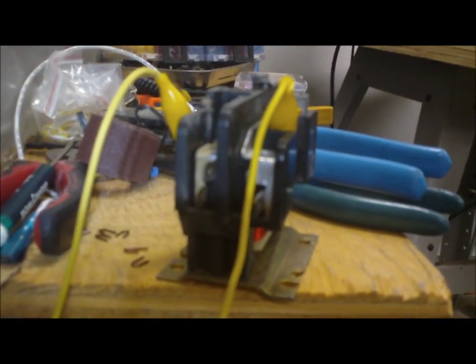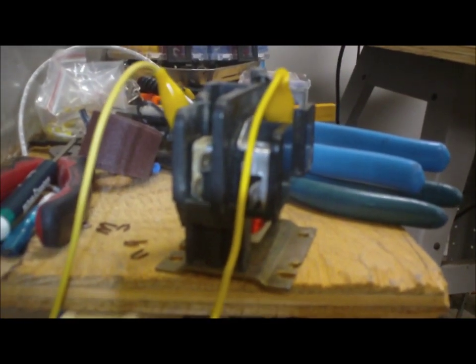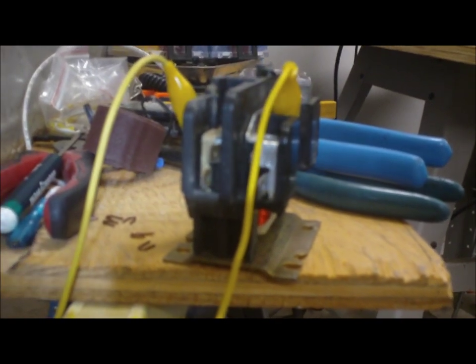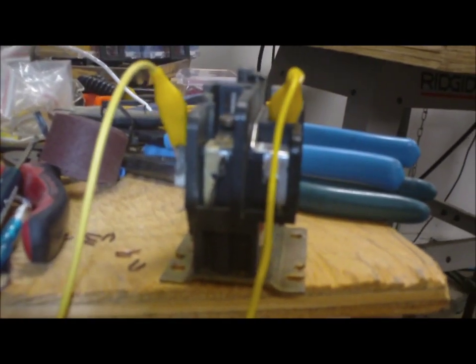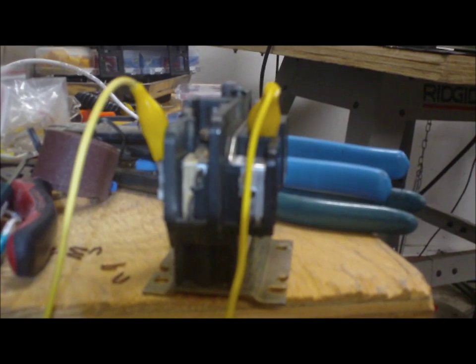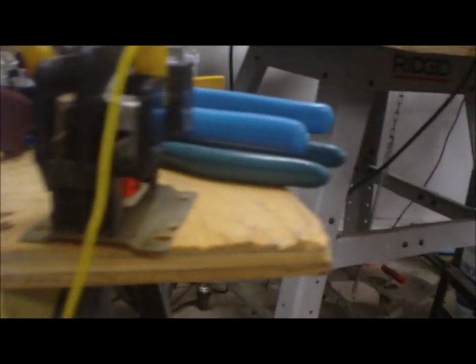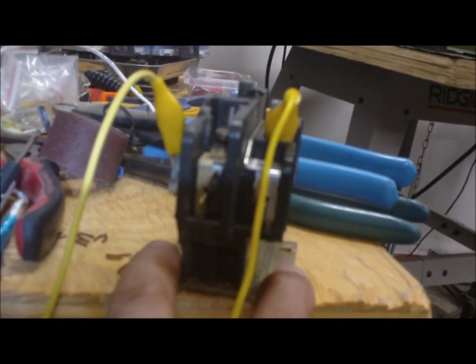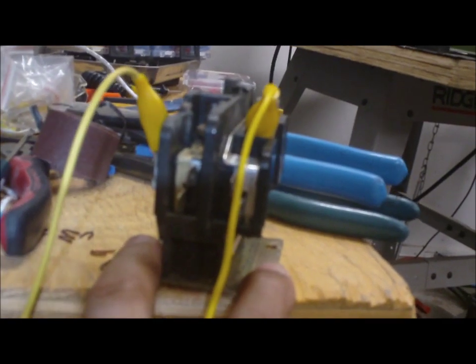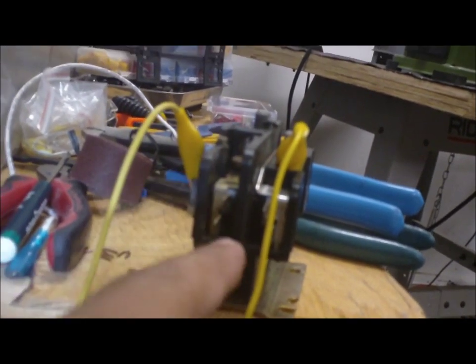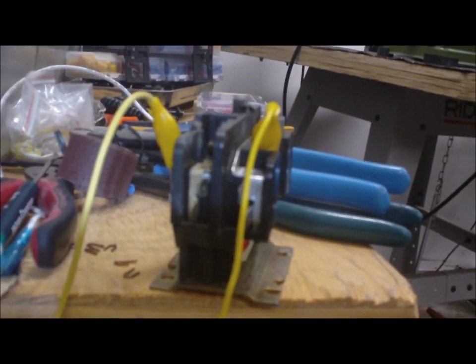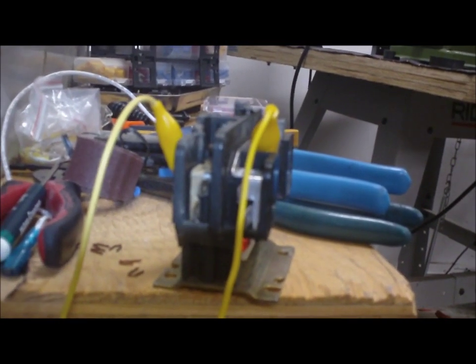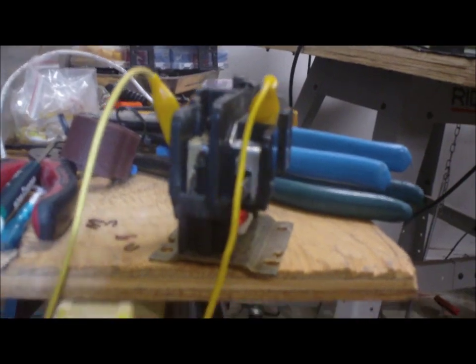And also right here I've got this contactor. Like I said, I picked this unit up with the condensing unit, and I tested out the contactor. It's a single pole. I wired it up to the 24 volts, that way when I fire it up and call for cooling, I just want to see if the contacts will close, and it does. It makes a lot of noise, buzzing and stuff, but it still pulls the contacts closed.